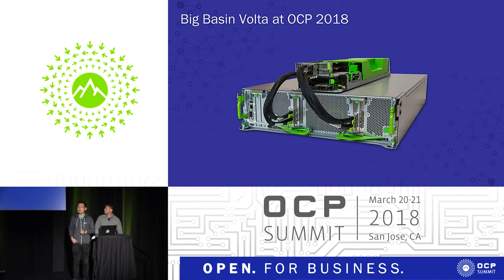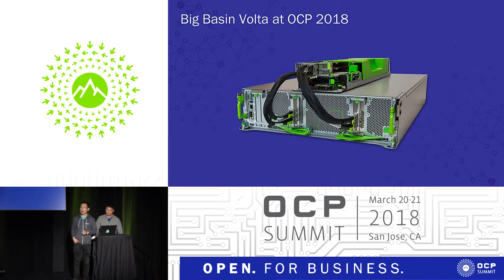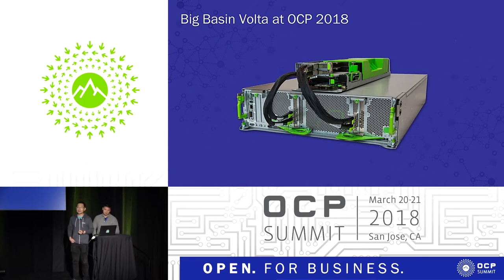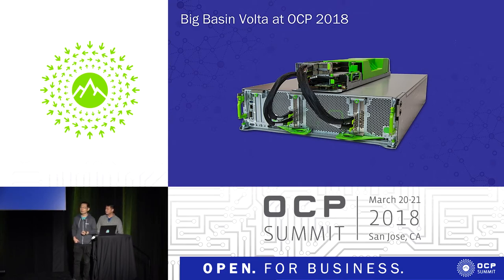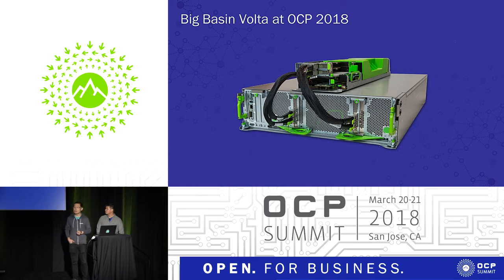Big Basin Volta is built on the same design philosophy. It is our second generation disaggregated design, which disaggregates the CPU compute head node from the GPU box. As we can see in the figure, the CPU head node sits on top of the GPU box, and they communicate via PCIe cable. This modular design allows us to take advantage of existing OCP components to build a customized design optimized for application performance, power efficiency, and total cost of ownership.